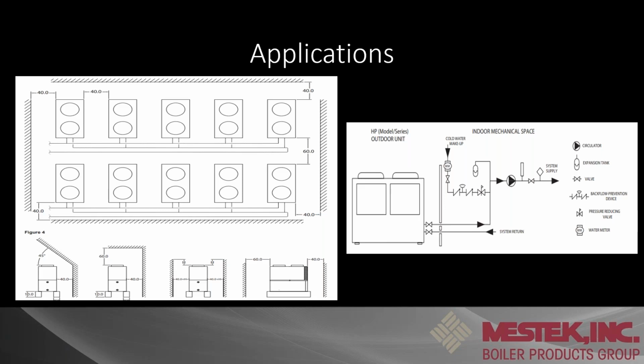Over to the right side is just a typical piping diagram, whether it's a primary, secondary, or variable flow, whatever it is there, it's just giving you an idea of how we want it. We always want to make sure we're pumping to our highest pressure drop, and that would be that shell and tube heat exchanger. So we're always pumping towards the unit, not away from the unit.